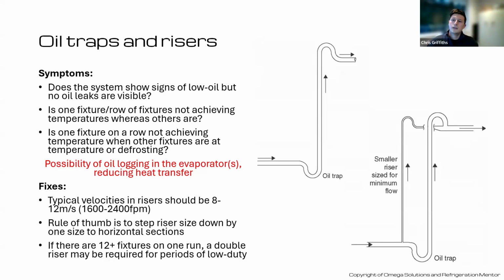Definitely. To be fair, Trevor, you've just touched on the first point there as well with this slide. Does the system show signs of low oil but no oil leaks are visible? Is one fixture or row of fixtures not achieving temperatures whereas others are? At least we can then pinpoint it down.